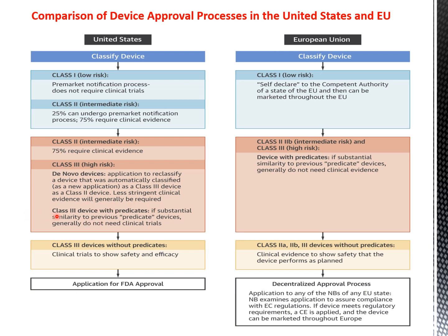And for Class 3 devices with predicates, if substantial similarity is seen, even for Class 3 devices, no clinical trials are required. And for Class 3 devices without predicates, clinical trials are required to show safety and efficacy. And finally, the manufacturer will file an application for the FDA approval. This is in US FDA, according to US FDA.